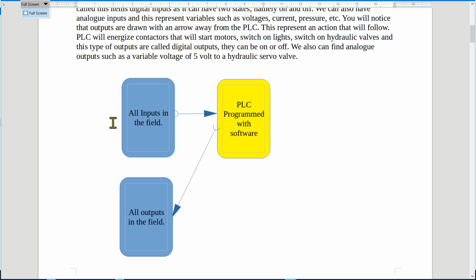Now you will remember that inputs, when we use a button, for example, with a PLC, we will supply one end of the button with 24 volt and the other point of the button, the other switching point, will be taken to the PLC. And that's why the arrow is clearly showing it from the inputs to the PLC. The PLC inside has got a software program that looks at the logic: if this and that, or this is at a high level, then the output must be switched. And that switches outputs in a field such as contactors.